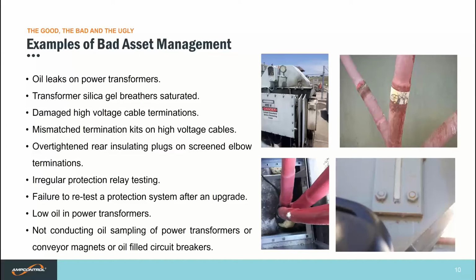Big issues we see on site are oil stains as opposed to oil leaks. It does not take a lot of oil, especially on a coal mine site, for a big black stain to cover a transformer. With older transformers, the type of gasket cord used was not that flexible. With aging, it becomes hard. Present corks are more of a nitrile rubber mix and offer way more flexibility for expansion and contraction. A simple maintenance procedure is to go around and nip up the lid bolts, the Buchholz bolts and the collars on the valve handles. With silica gel breathers, the design has changed and improved over the years, with many of the smaller Coke bottle types not having an oil bath anymore.